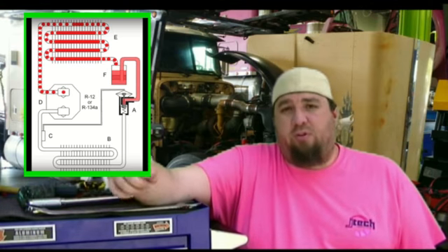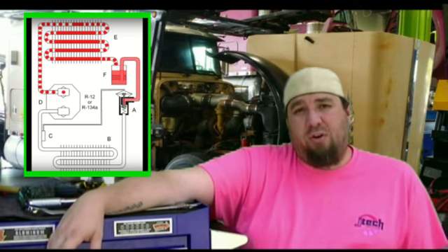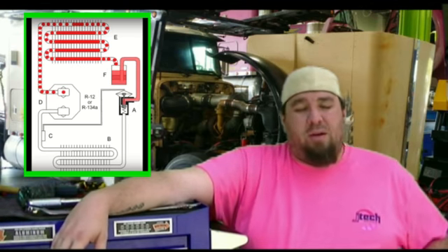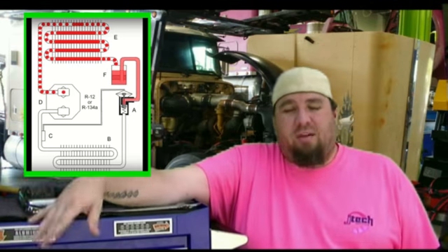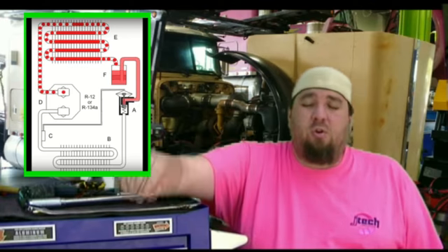Now, only the liquid refrigerant will pass through the pickup tube. But the first part of the receiver is pretty much a storage tank. So once it's passed through the desiccant filter, it is picked up by the pickup tube. This unit also would contain usually a sight glass, so that you can look for discoloration, cloudiness or anything like that. Usually cloudiness will be moisture that has gotten past the desiccant filter, which means your desiccant filter probably needs changed.